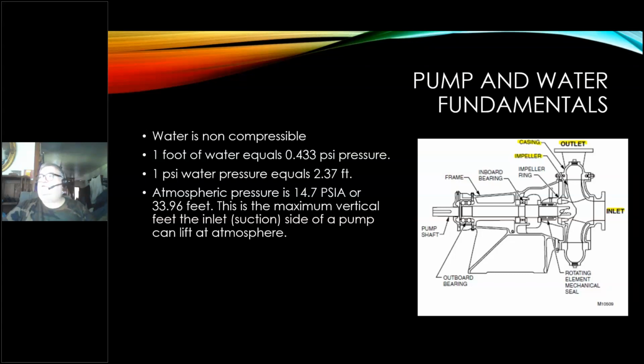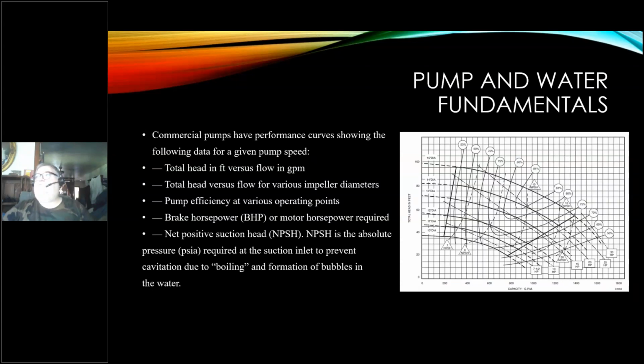Now on this graphic, I've highlighted the critical parts: the inlet, the outlet, the casing of the pump, which could be a standard casing, but the impeller is the part that rotates inside the casing, and that's the part that makes the curves. So when we look at a pump curve, you're seeing different impellers on this same curve. Commercial pumps have performance curves showing the following data for a given pump speed. Now remember, the pump curves are made at full speed.